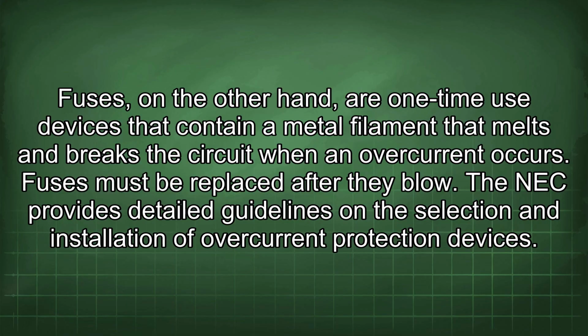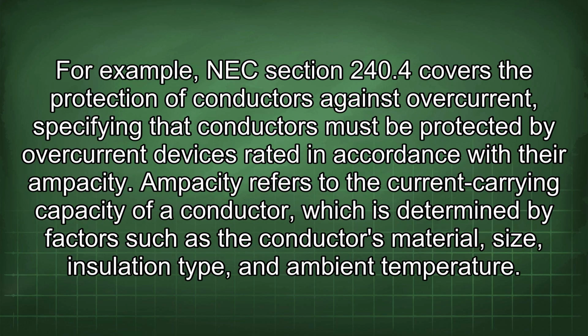The NEC provides detailed guidelines on the selection and installation of overcurrent protection devices. For example, NEC Section 240.4 covers the protection of conductors against overcurrent, specifying that conductors must be protected by overcurrent devices rated in accordance with their ampacity. Ampacity refers to the current carrying capacity of a conductor, which is determined by factors such as the conductor's material, size, insulation type, and the ambient temperature.